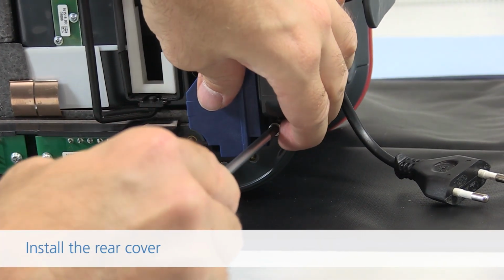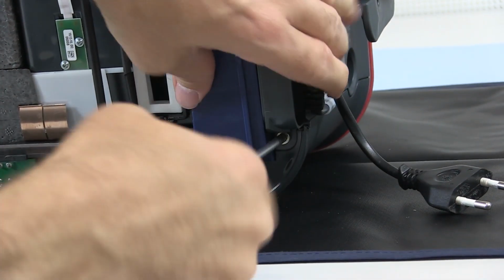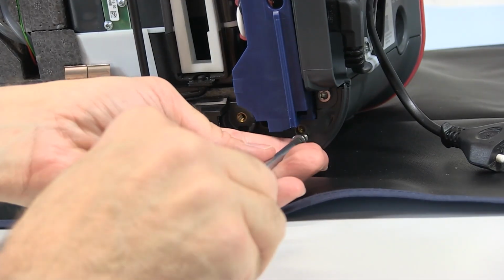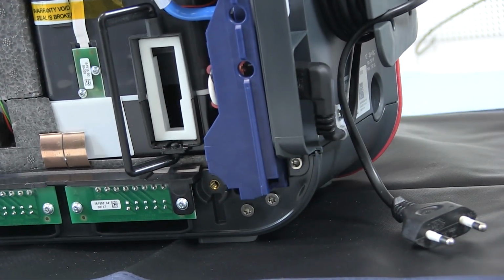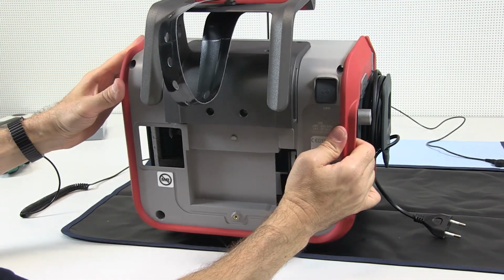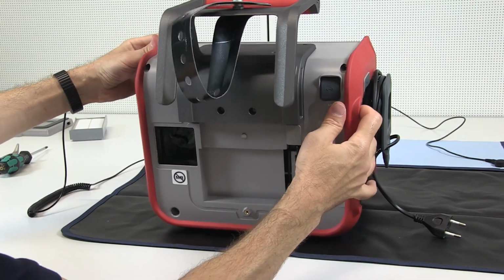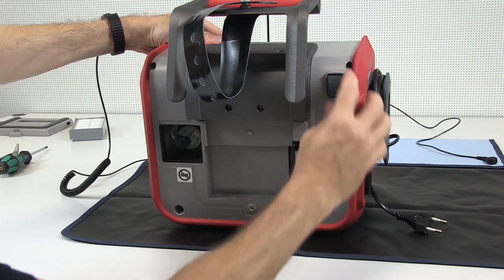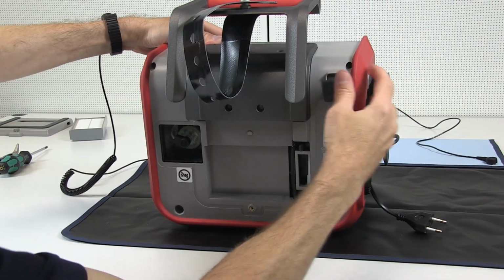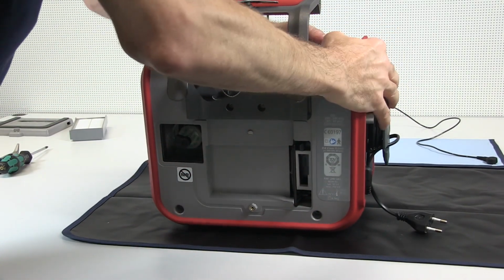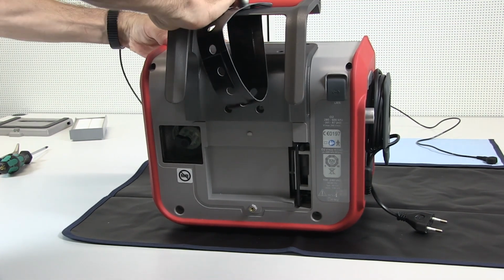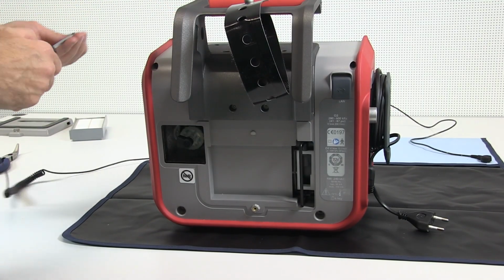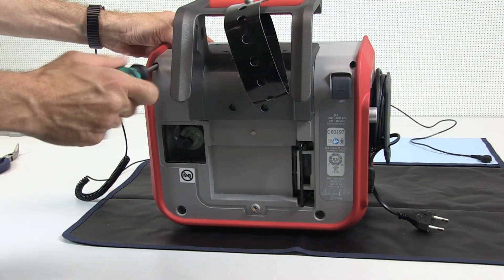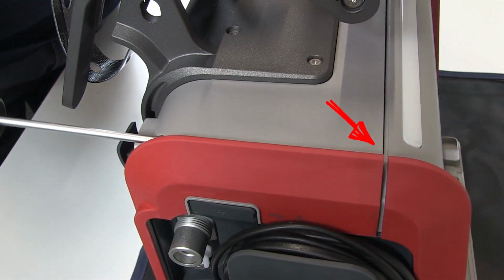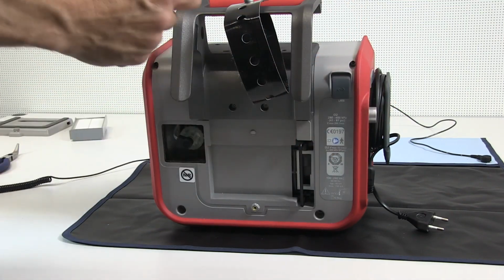Install the 2 screws on the rear side of the device, then put the rear cover into position. Open the LAN port cover. Install the 2 screws at the top of the rear, making sure the front and rear covers fit together closely while you tighten the 2 top screws. Install the 2 screws at the bottom of the rear, then tighten them.